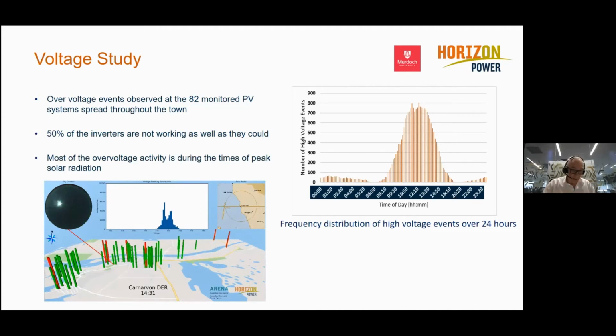Here in Australia, there's a great deal of discussion around using inverter control at a primary level by adjusting response curves in the inverters themselves. So we started to explore how we could use reactive power droop curves to manage over-voltage events on the network. What we discovered was unexpected and initially very interesting, but at the end of the day quite obvious, and I'll explain why on the following slides.